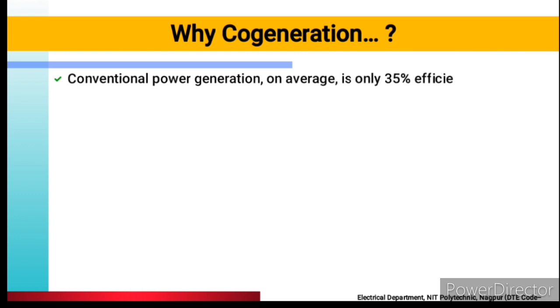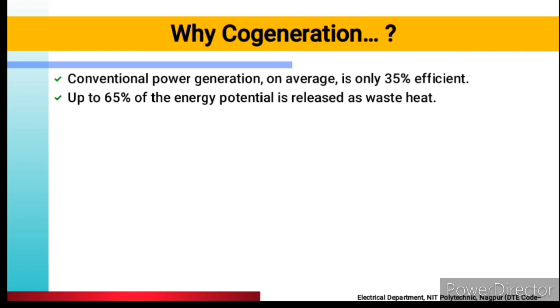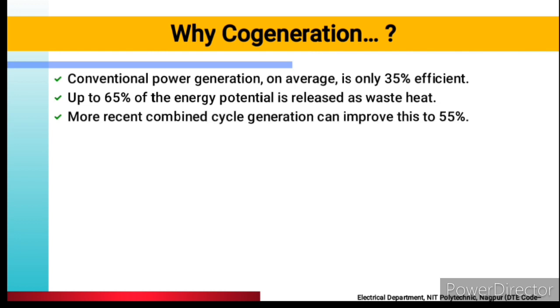A conventional power plant provides only about 35% efficient energy; up to 65% of energy potential is released as waste heat. When you are using a fuel of 100%, only 35% of energy is generated and 65% is totally wasted. More recent combined cycle generation can improve this to 55%. If we use co-generation, which is also called combined cycle generation, we can improve efficiency from 35% up to 55%.